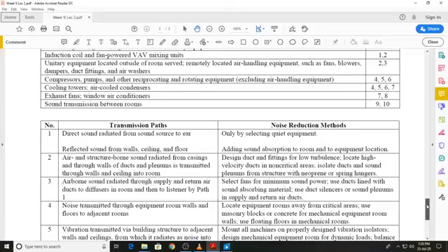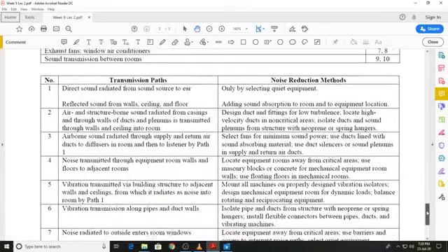So for example, if you look at a compressor that is running in the plant room, it will have typical noise transmission paths 4, 5 and 6. And if you look at this table, 4 is noise transmitted through equipment room walls and floors to adjacent rooms. 5 is vibration transmitted through the building structure, and 6 is vibration transmission along pipes and duct walls. So there will be 3 paths through which noise will be propagated when a compressor is running, and for each there are certain recommendations for reducing those noise levels.